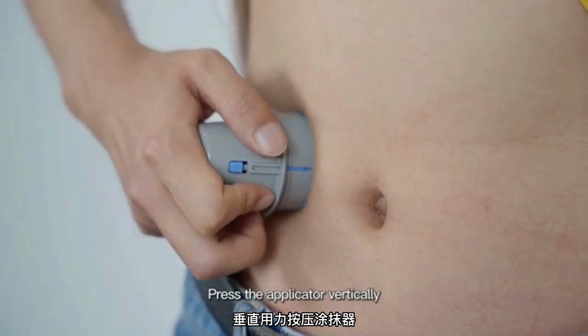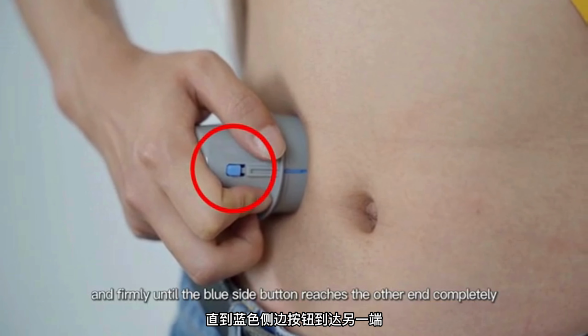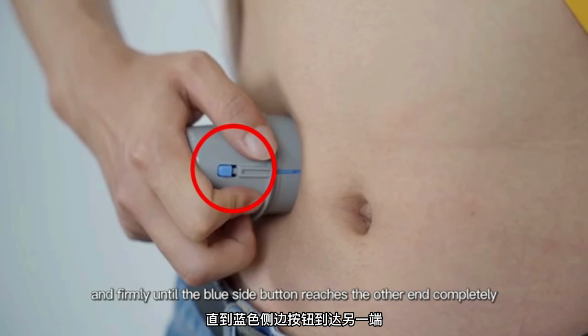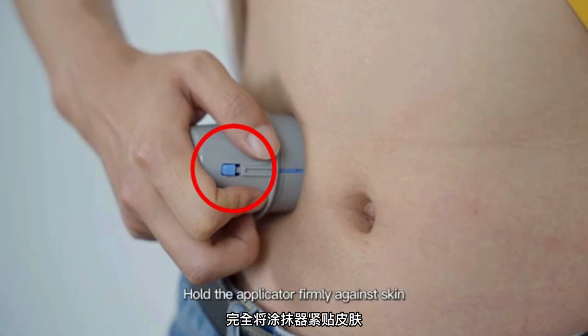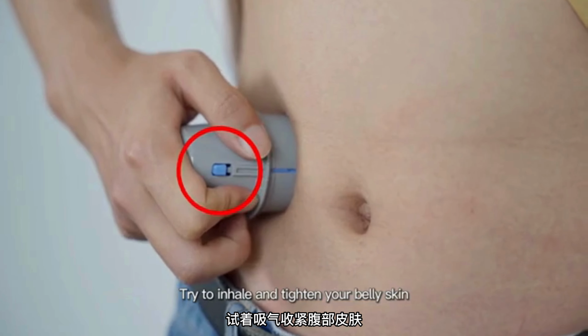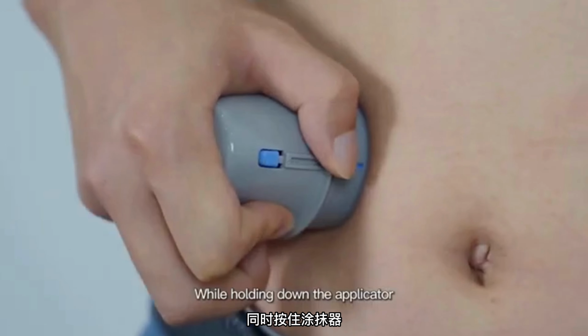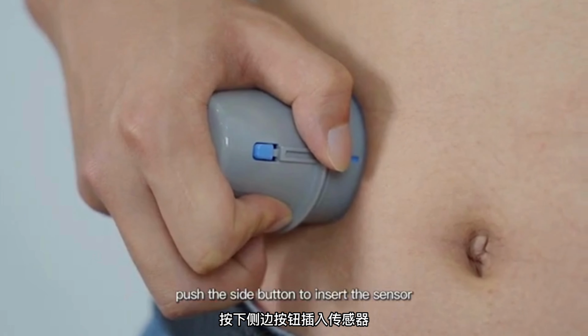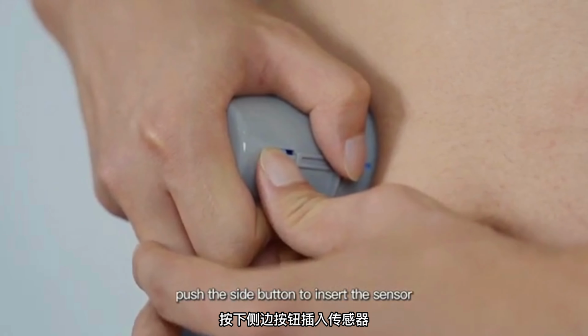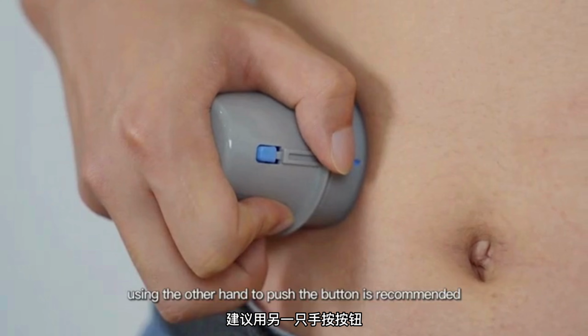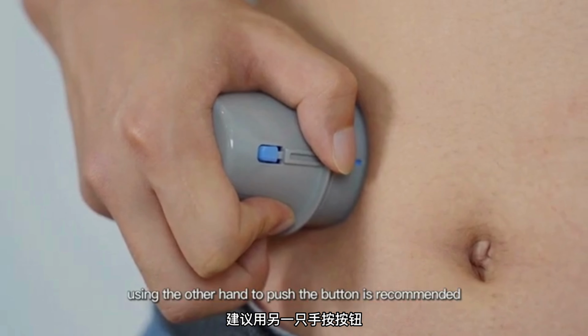Press the applicator vertically and firmly until the blue side button reaches the other end completely. Hold the applicator firmly against the skin. Try to inhale and tighten your belly skin. While holding down the applicator, push the side button to insert the sensor. For new users, using the other hand to push the button is recommended.